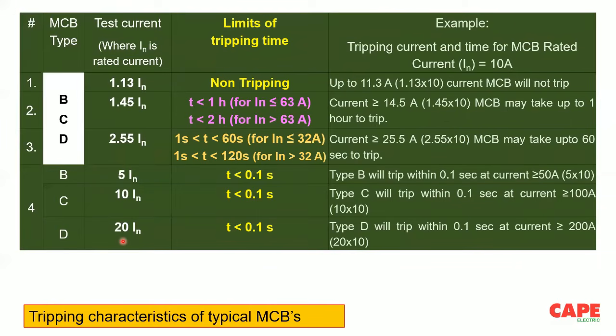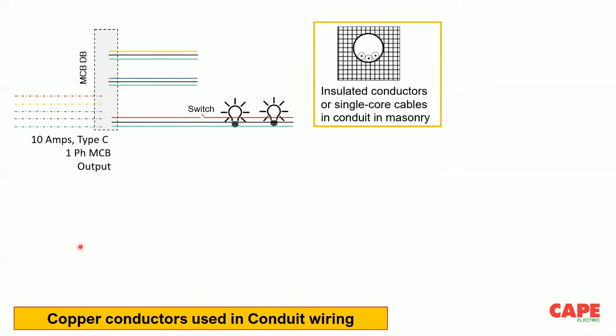So basically, these three types of MCBs must be selected appropriately for a certain location. For example, in a residential application, MCBs are there to protect the wiring of the installation, not your equipment. In residential distribution, especially in the final circuits, we are supposed to use the Type B MCB. Type B MCB is safer because it can trip instantaneously even at a lesser current. This means even if the impedance of the circuit is a little higher, this MCB is efficient, because each instantaneous tripping current is related to the impedance of the circuit. So Type B MCB is very much necessary for residential application. Of course, for industrial, it's a little different. But whatever type of MCB you use, you have to size the conductor accordingly and have the impedance accordingly.